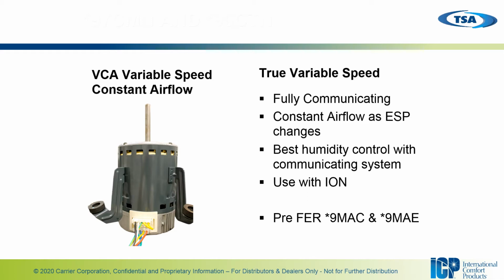As it receives the feedback of the RPM, it can make its adjustments to overcome additional static pressure, to a certain extent. You're also going to get the best humidity control with this type of blower, a communicating type blower. And as you use it with our communicating controls, like the Ion or the Observer, it will give you the best control for the best comfort in the home.